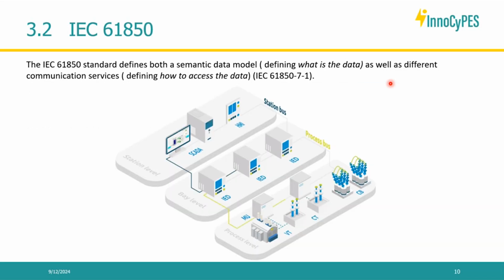I'll show a moving GIF that shows the segregation of networks in a 61850 substation. At the very bottom you have the instruments - circuit breakers, current transformers, voltage transformers - which are the physical processes. Then you have the first communication bus, called the process bus, which gets digitized current and voltage information from merging units.